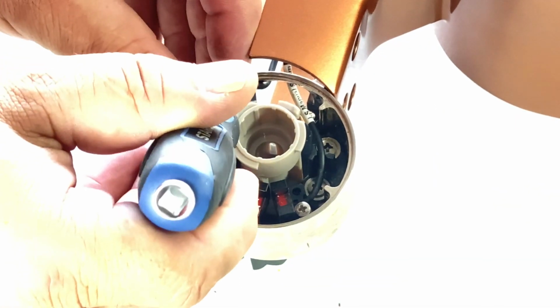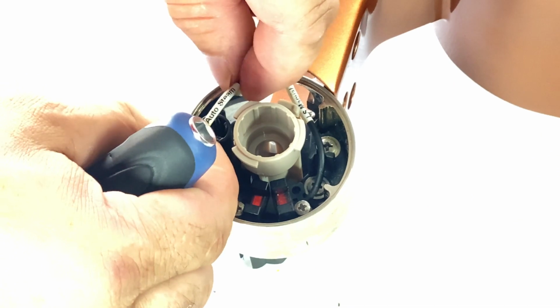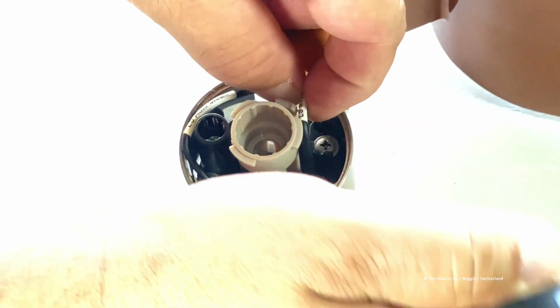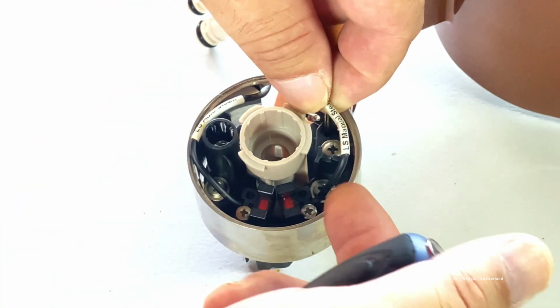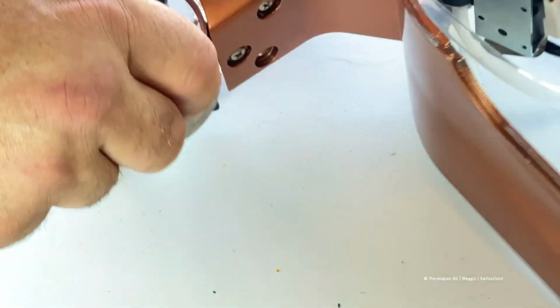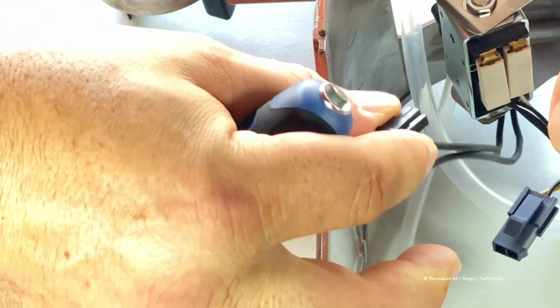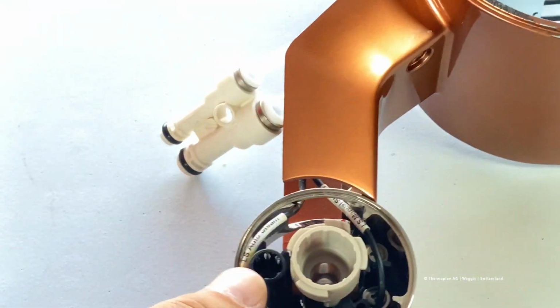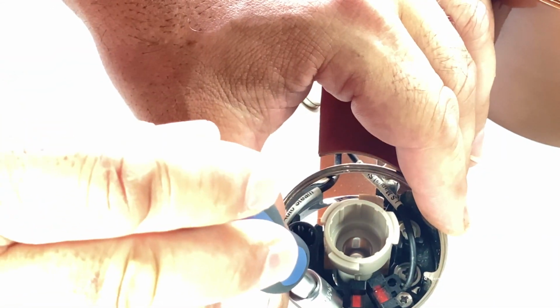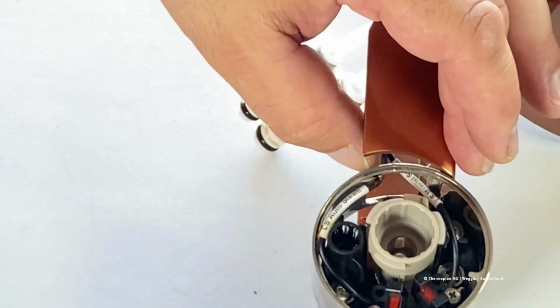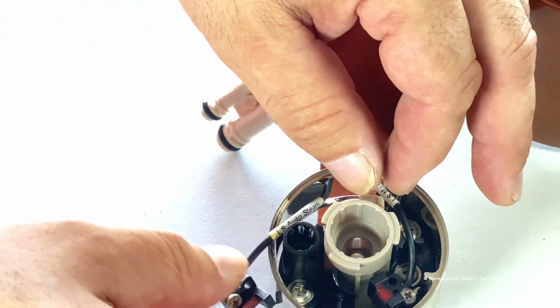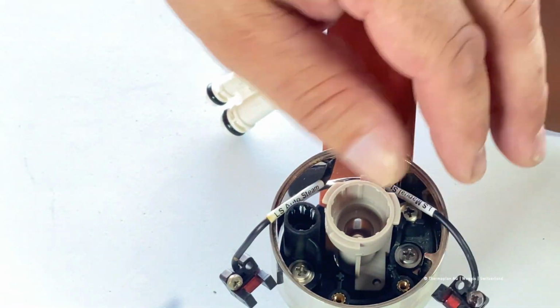Next, if you have an issue with the photoelectric sensor, here is how they are routed. You see on the upper position auto steam and on the down position it's the manual steam. This is very important when you change that harness. So if you change, you need to disconnect it here by this plug. Then you take off those two small Phillips head screws. Each sensor has one screw. Important, the label, maybe make a picture prior to taking off this little harness.